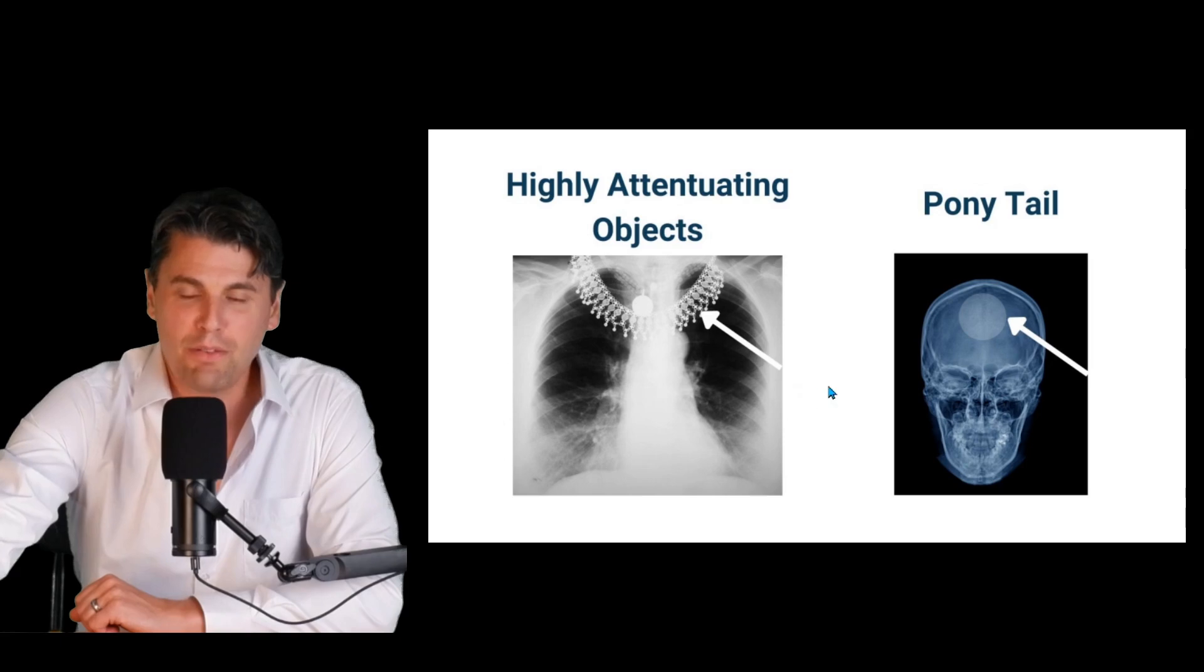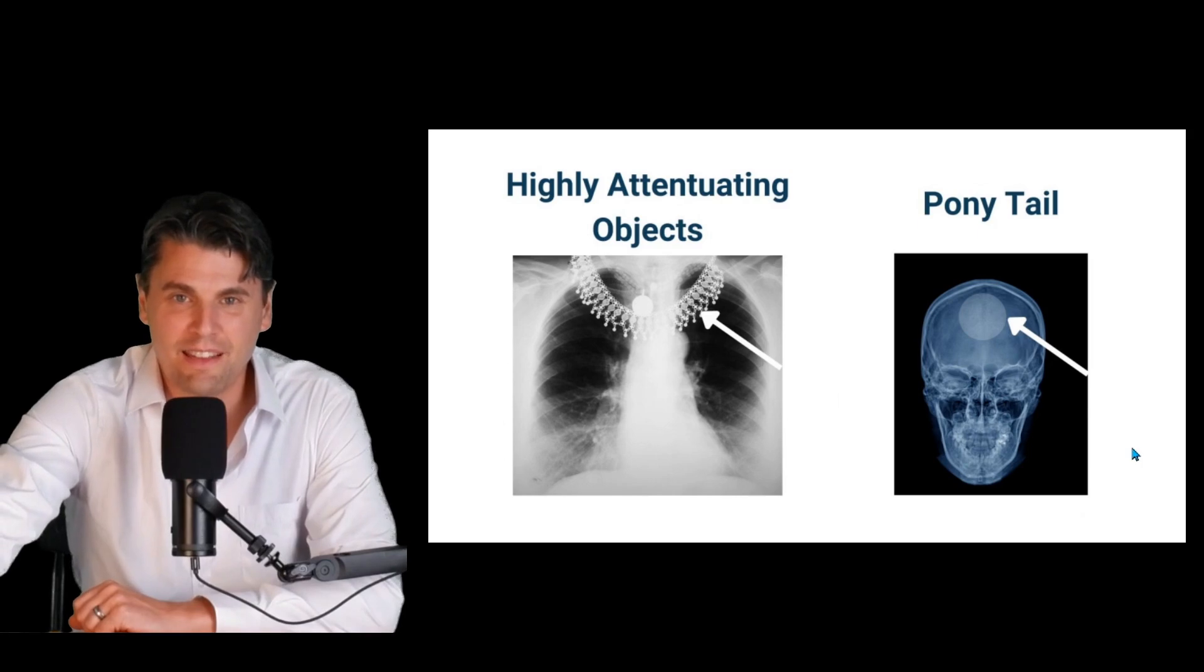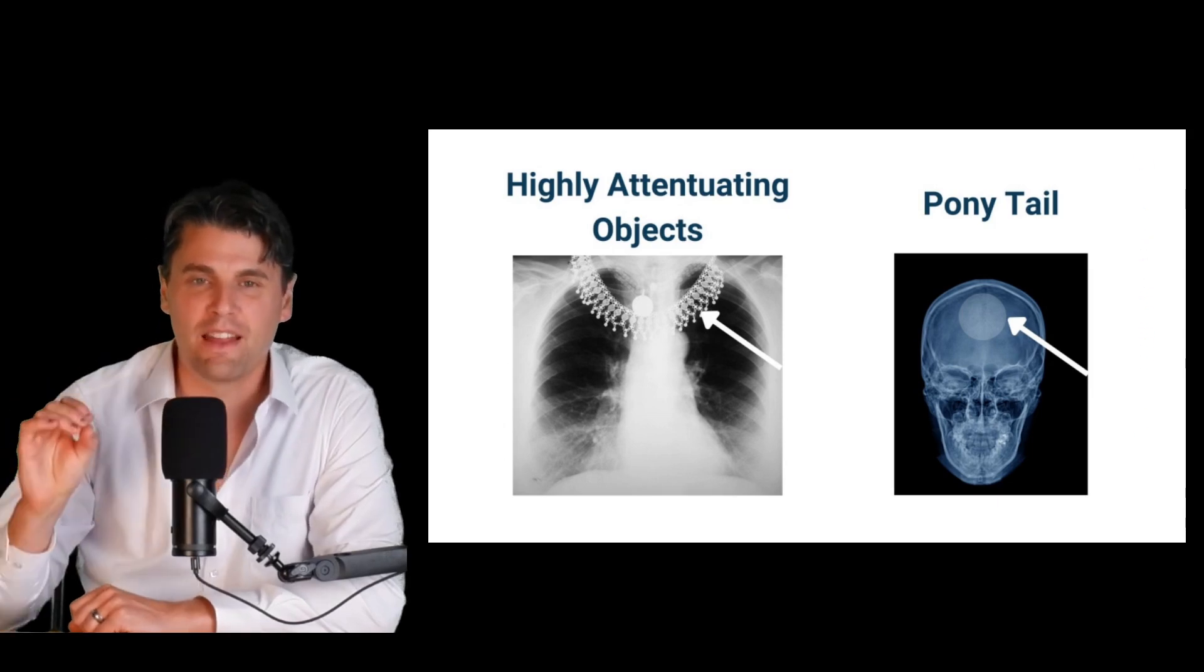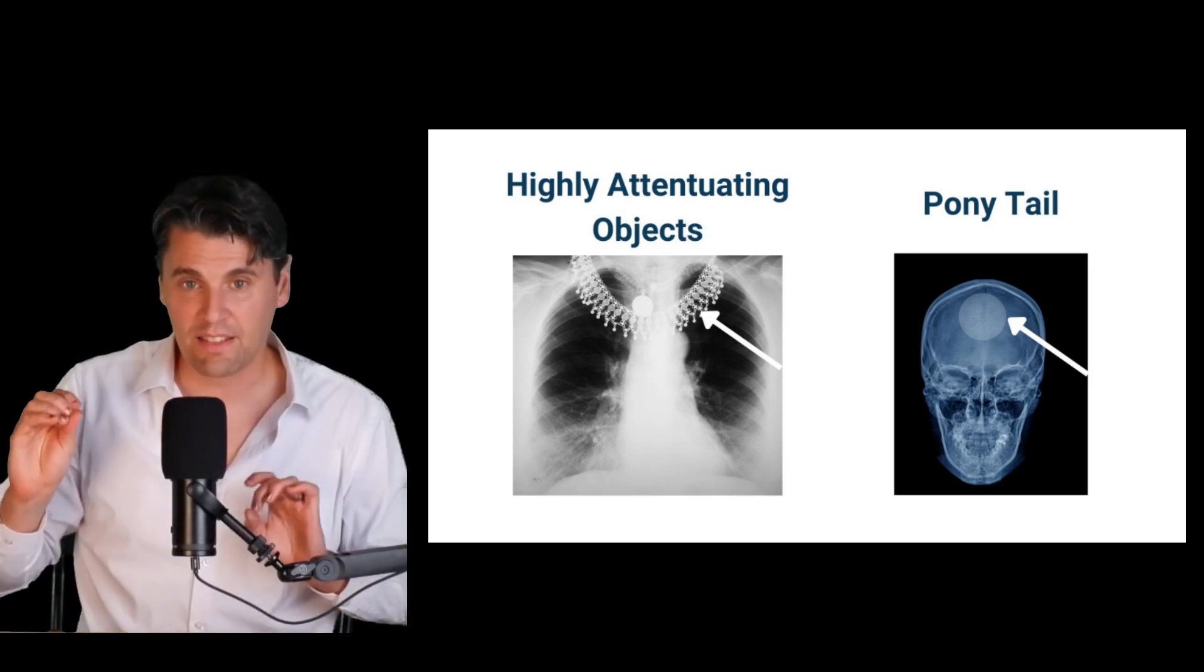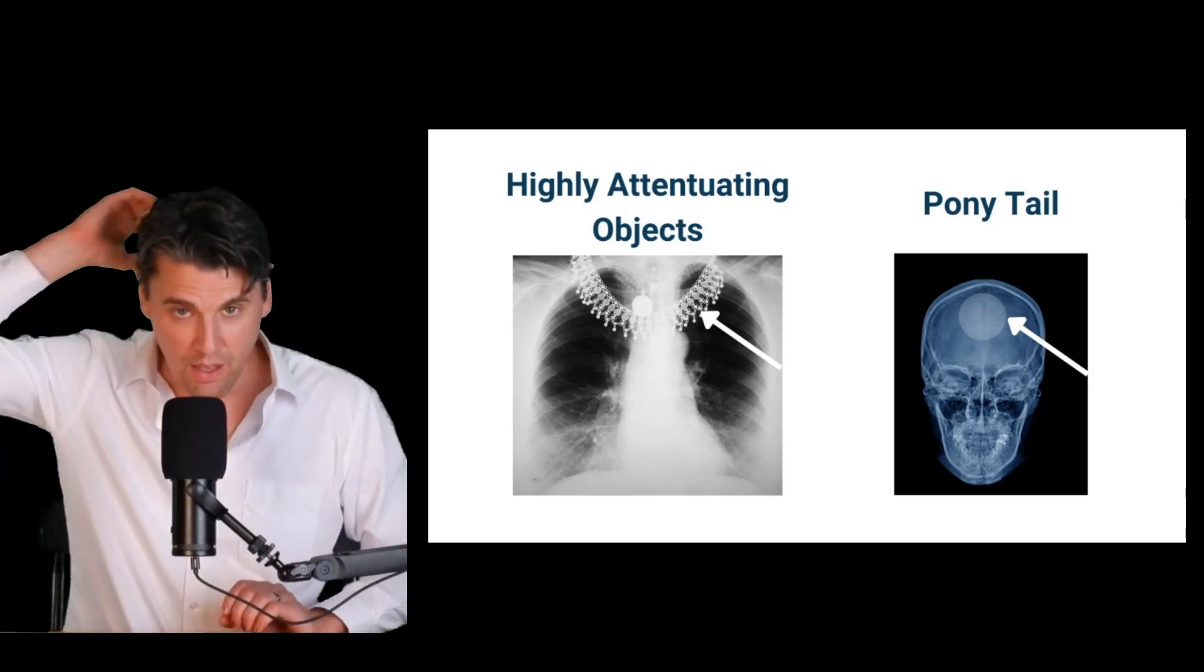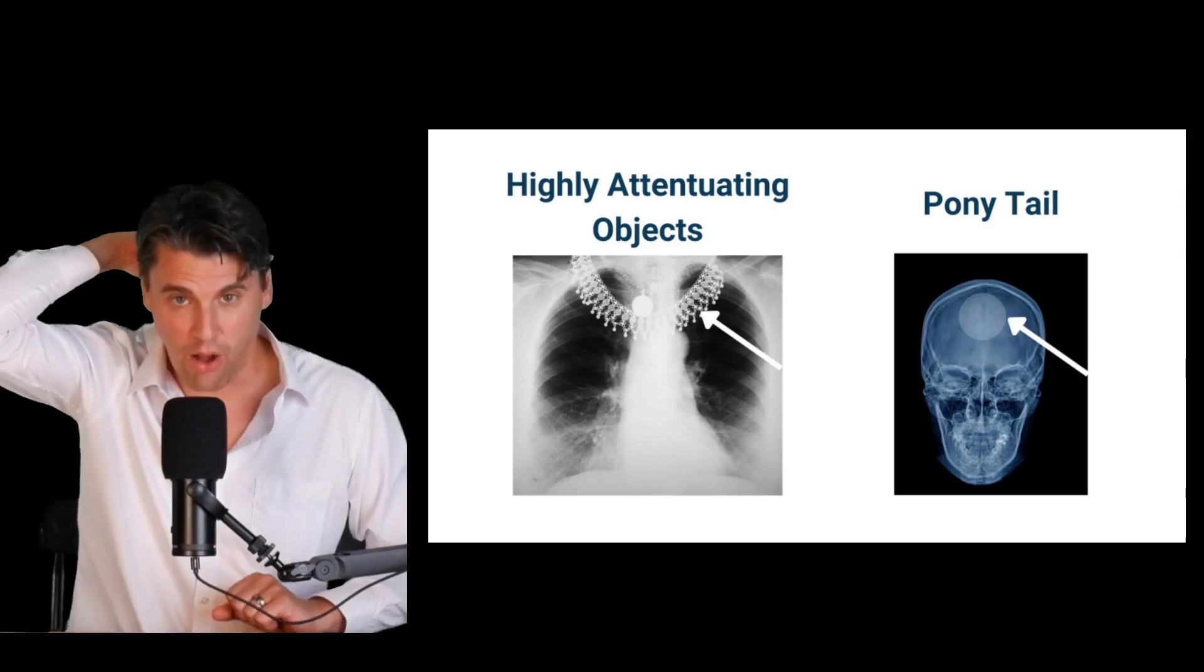Something else which actually I personally didn't think of before I started in this is hair. Hair can actually be attenuating. And when that hair is all in one place, if you have lots of dreadlocks, or in this case, if you have a ponytail, that ponytail is going to lead to more attenuation that's all in one place.